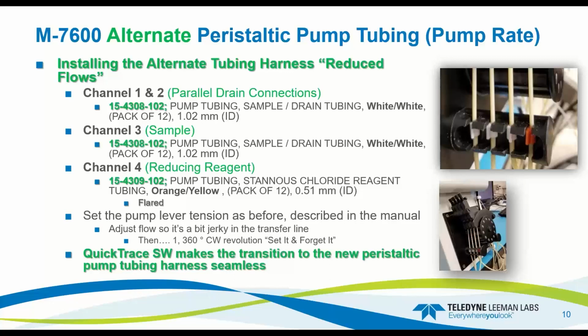Now the pump tubing. Okay, so let's dive in here a little bit. So during this process, we wanted to keep all the ratios the same. By those ratios, I mean the reagent and the sample as they compare to each other. So we didn't change anything within the system, since how it's been operating for so many years under precise and ideal conditions. Let me stop here for a second and get you to look at the part numbers. So part number 15-4308-102, that is the white over here, and that's for the drain. And then the same pump tube number is for the sample.